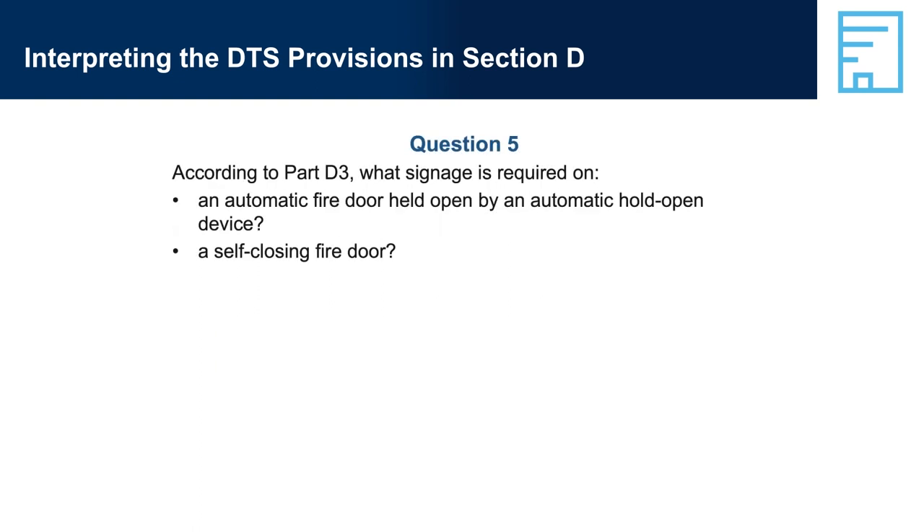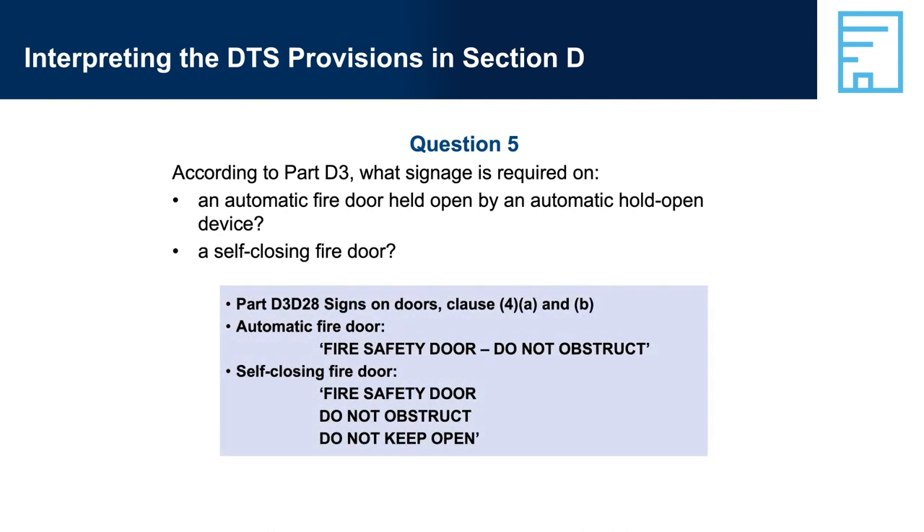Question 5: According to Part D3, what signage is required on an automatic door held open by an automatic hold-open device, and on a self-closing door? Answer 5: Part D3-D28, Signs on Doors, Clauses 4A and B.